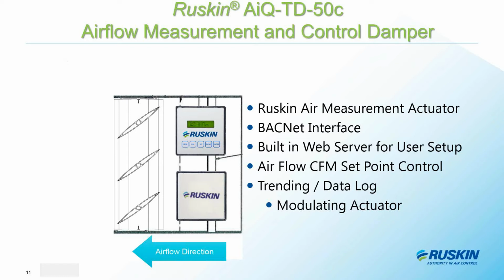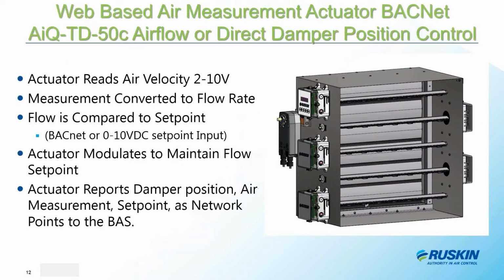So that was a lot of spelling for you, but basically we had models in the past that included air measurement with controls, and we're saying that this is the new product and it will replace and provide you air measurement with control, but no longer do you have a control box, you just simply have an actuator, and that actuator has the controls built into it. So that's what the TD50C does for us. With the C, we're adding this air measurement actuator.